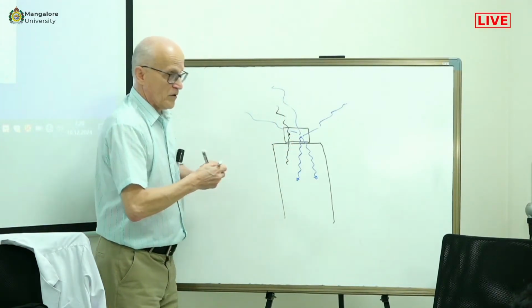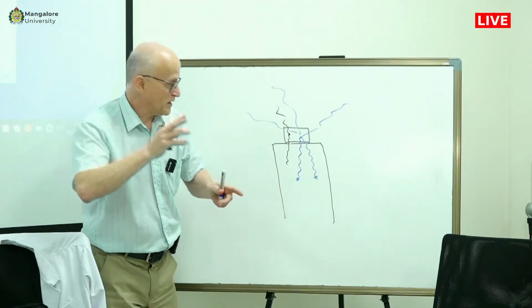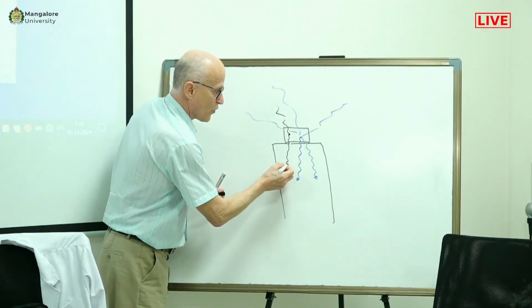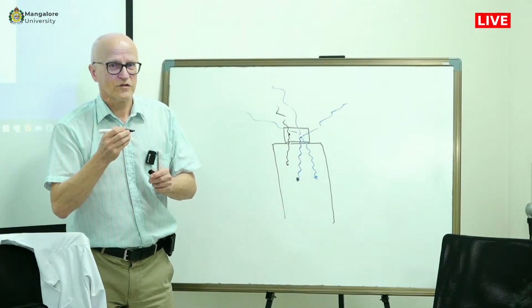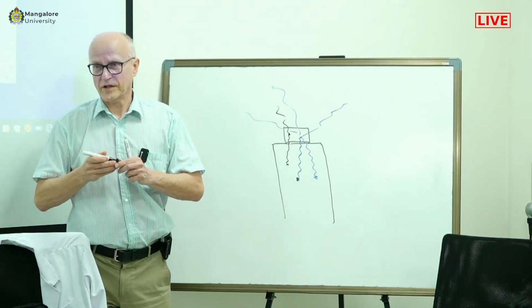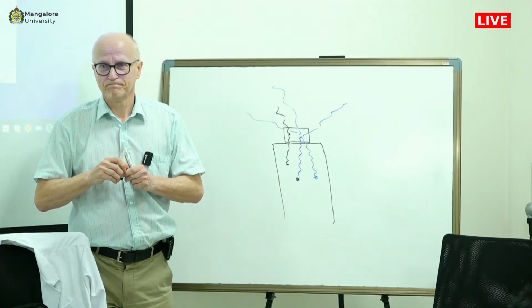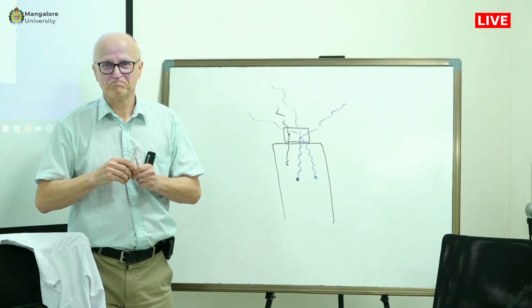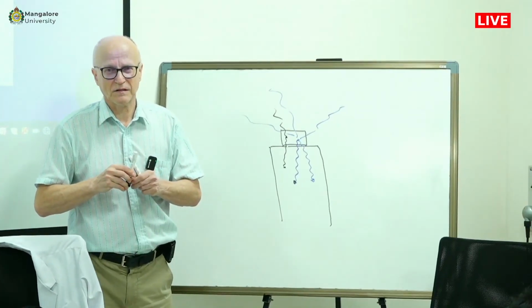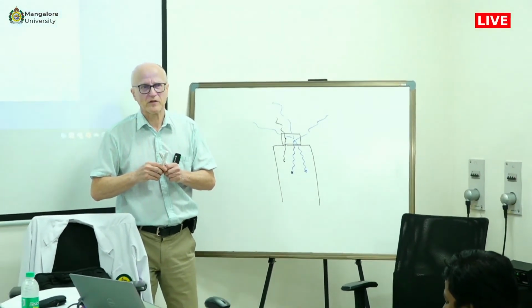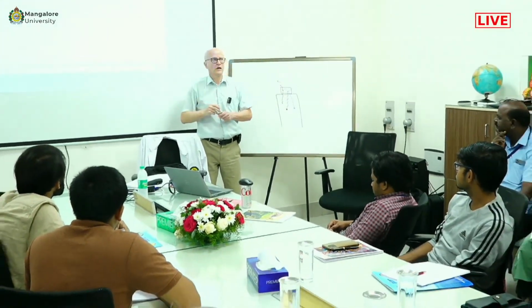However, because the time resolution is only of the order of 1 microsecond in the MCA, it may happen that this photon is detected at the same time as this photon. So this is so-called random coincidence. It's a very nasty phenomenon, and it sometimes causes very big problems in the spectrum analysis, especially if there are several peaks in the spectrum.